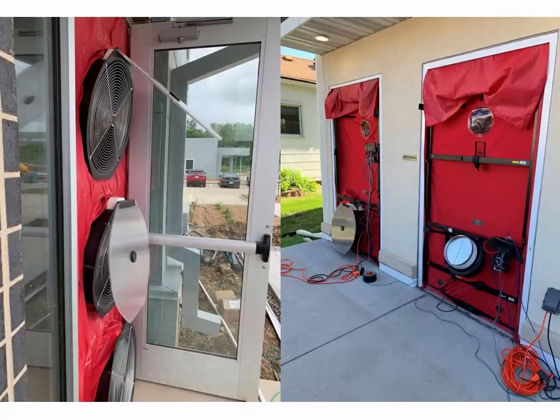Here we can see that damper in action. You notice it's actually just a lightweight piece of plexiglass taped to the fan with a magnet in the center. So when the fan starts up, it builds up pressure and pops that open. And then when the fan turns off, the damper just shuts and connects right to the center of the fan with the magnet. By having a fan that would cap and uncap itself, it really streamlined our process because we didn't need to have someone running around to each fan location to cap and uncap for each baseline measurement.